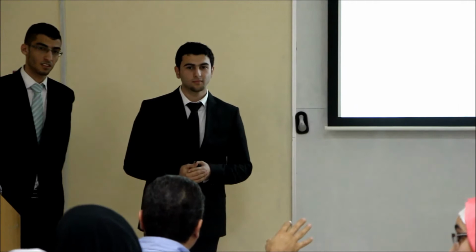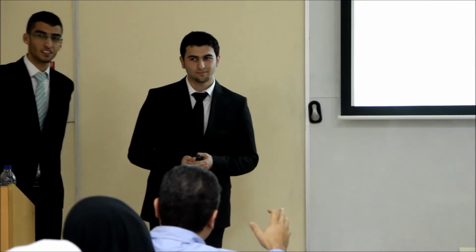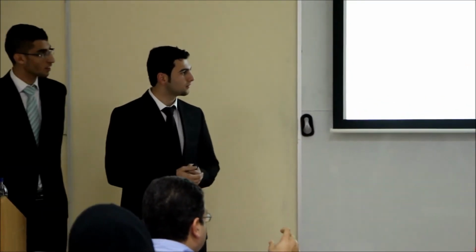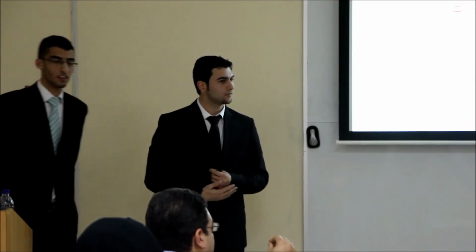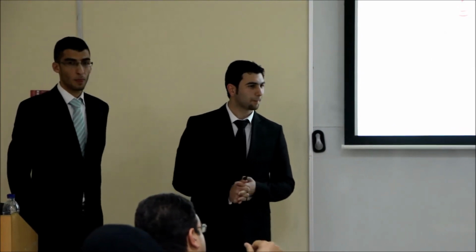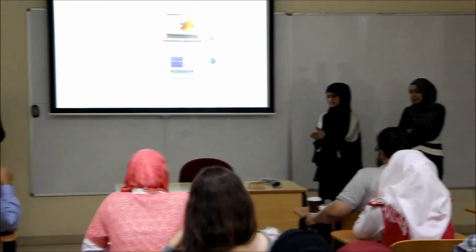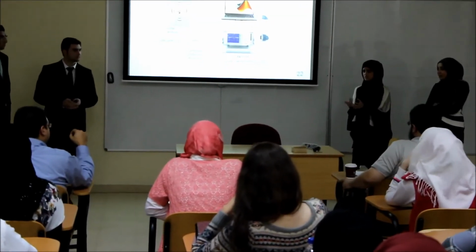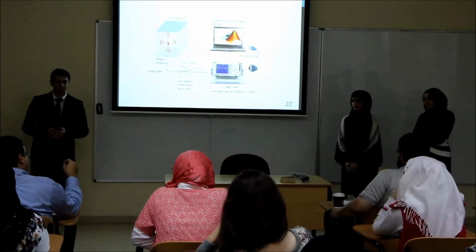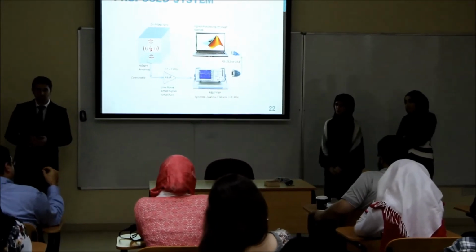This is what you are going to do. Basically, yeah. In the lab. But you are going to lose some of the oil, right? Some of the oil in what sense? Like when you open the valve. They do open it for DGA, for refilling, or when they want to do the DGA analysis for the oil, they take a sample from it. So a small portion would not matter. Yeah, I mean the time for the installation. But it wouldn't take a lot of time, so we're only going to insert it and close the valve instantly.